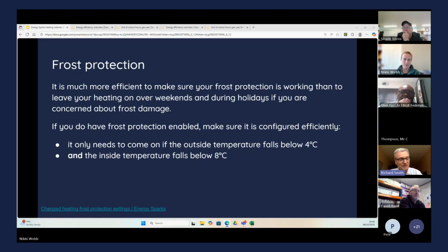The caveat is you know your school. You may have an old school that suffers from condensation - mine does - and you know that 8 degrees doesn't do it, because you'll get mold, which is a bigger cost to fix than keeping it warmer. So if you know you need a zone up to 10 or 12 to keep the building's integrity, then do it. You get to know your school well, and so you know what temperatures you need to keep it right and save yourself a lot of work.